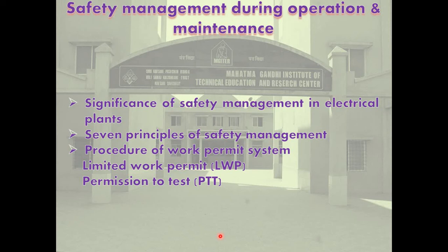During maintenance, the risk of accident exists due to lapses in work permit systems, live parts in the neighborhood, not closing of earthing switches while working, entering corroding areas in dangerous zones, etc. Electrical systems and plants have built-in safeguards against abnormal operating conditions, faults, wrong switching, fire, etc. Protective systems detect many abnormal conditions and give alarm. Switchgear operates automatically and clears the faulty system from the rest of the system. Switchgear and control gear have several interlocks. Sequential switching devices are safeguards to prevent wrong operations and accidents.